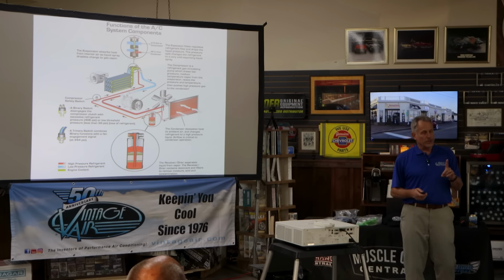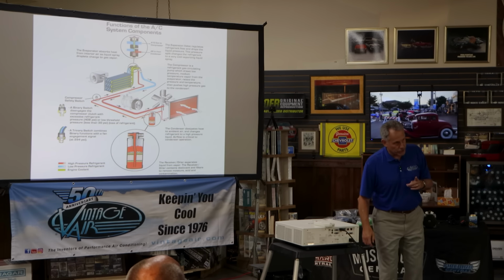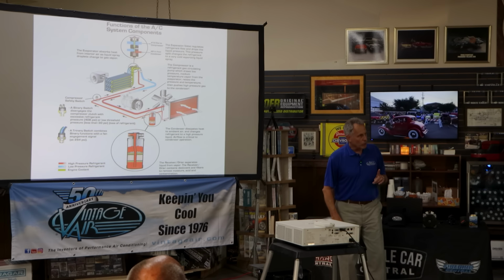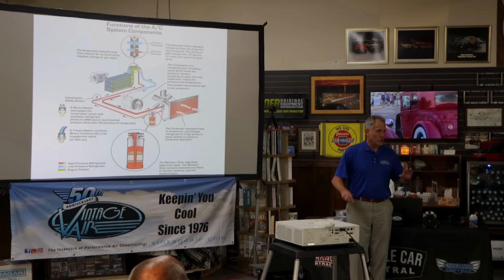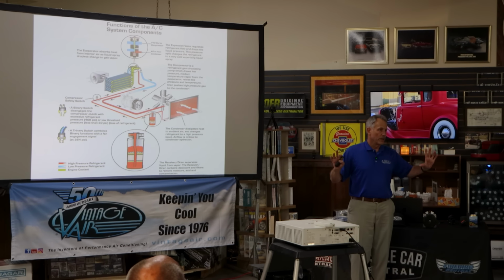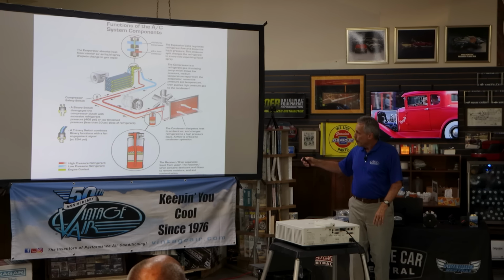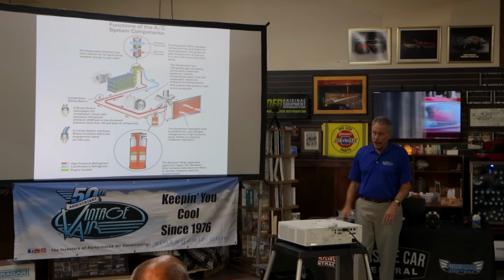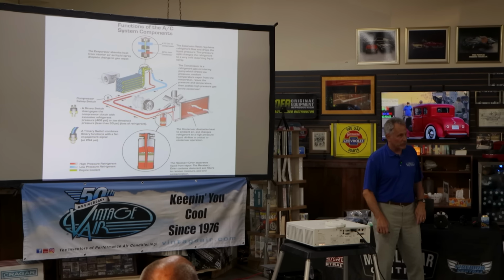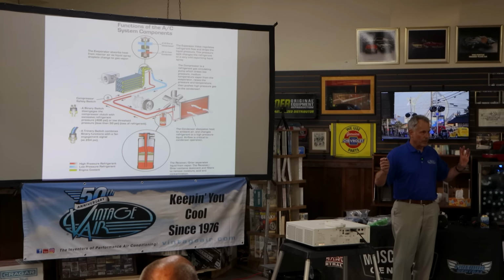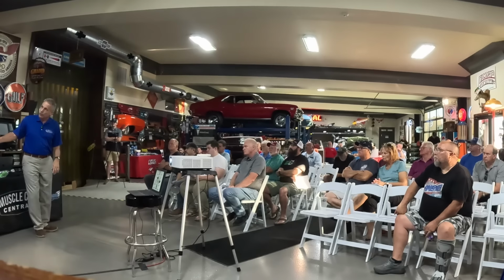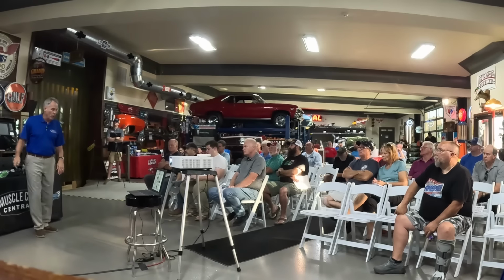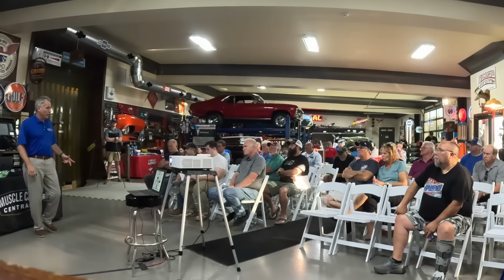One way you can always tell if you've got an external freeze up on your system is the blower will get really loud, but you're not feeling much air coming out your vents because it's trying to blow through a frozen coil. So the air you feel is going to be basically stagnant, real stale feeling air, because all you're getting is whatever air can be forced around the coil, under it or around it.